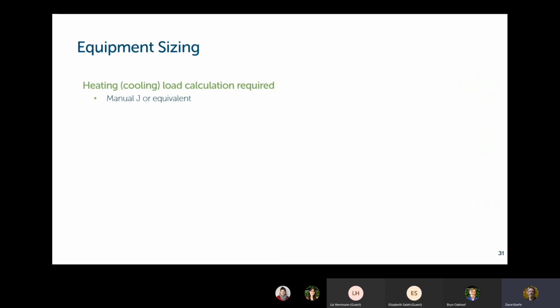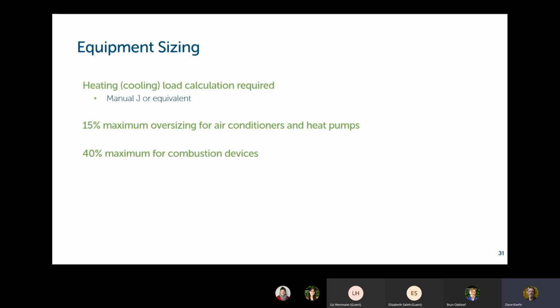Manual J is the industry standard for this. It's been used in the heating industry for decades. Any competent heating contractor should be familiar with Manual J and should be able to present the Manual J calculations, whether they do it themselves or they have their suppliers do it. You can do it on paper, you can do it on the computer. Lots of options, but the code says it's supposed to be done. And then the code says you're supposed to put in equipment that's informed by that information. So if you're putting in air conditioners and heat pumps, you shouldn't be putting in a machine that's any more than 15% bigger than what Manual J told you you needed. If you're doing combustion devices, that is fossil fuel devices where you're burning something, you're not allowed to put in any equipment that's more than 40% bigger than is required according to the heat load calculations.